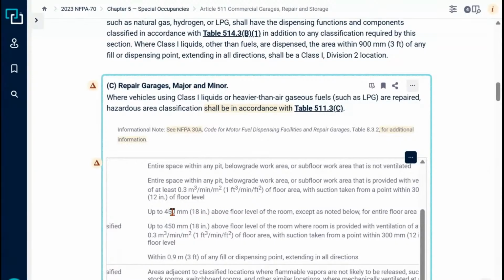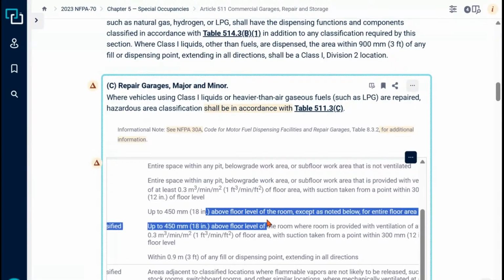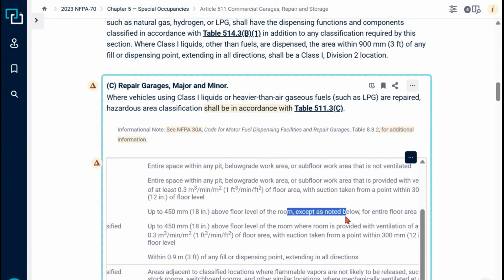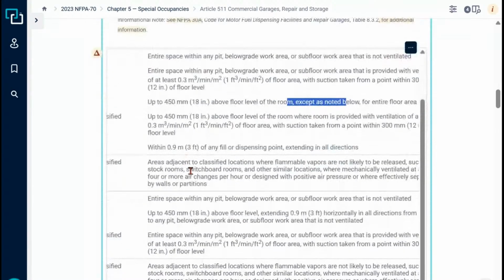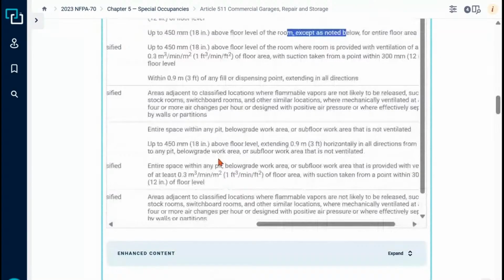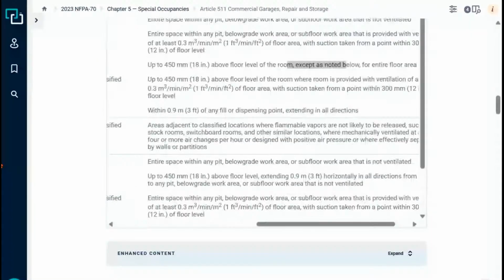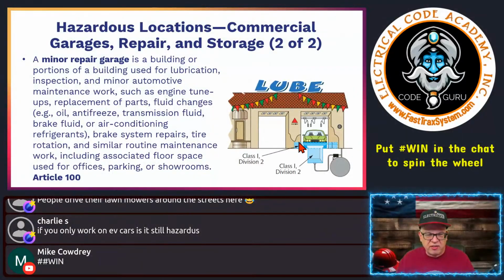That's where you heard me say 18 inches, right? So 18 inches above the floor level of the room, except as noted below. Here are all your conditions - we're not going into all of these. But if you look at the illustration, since it doesn't have fuel, this would be a class 1 division 2 location, and up to 18 inches above the floor would also be class 1 division 2. So it's going to extend out of the garage.